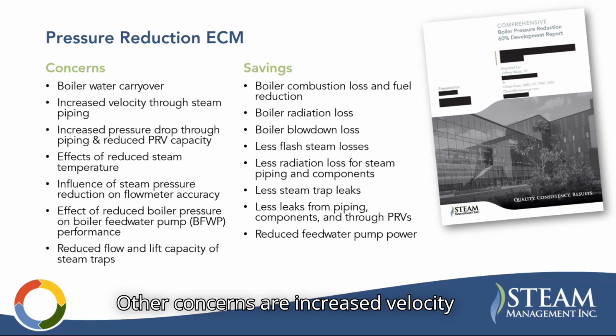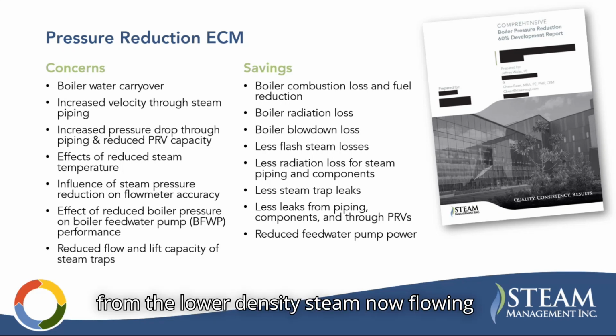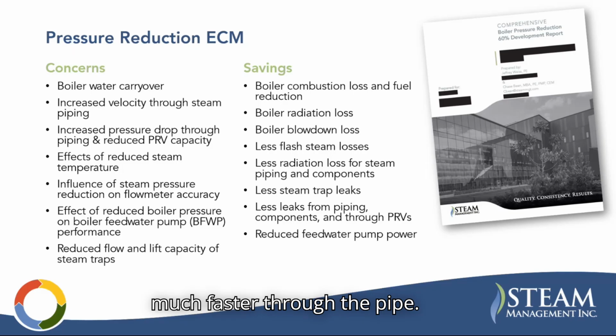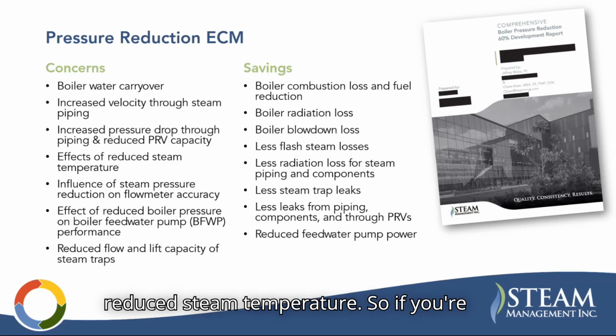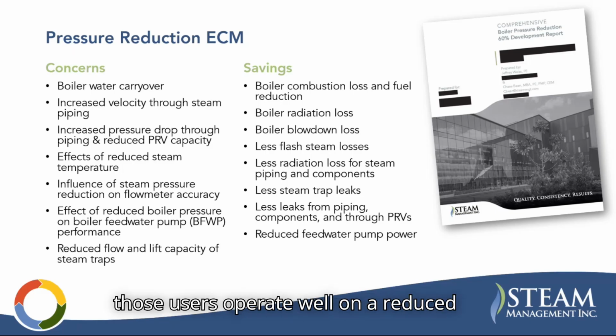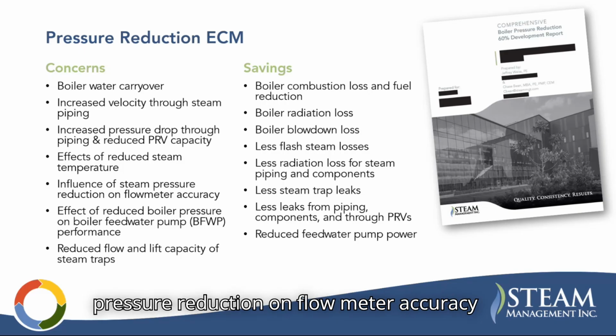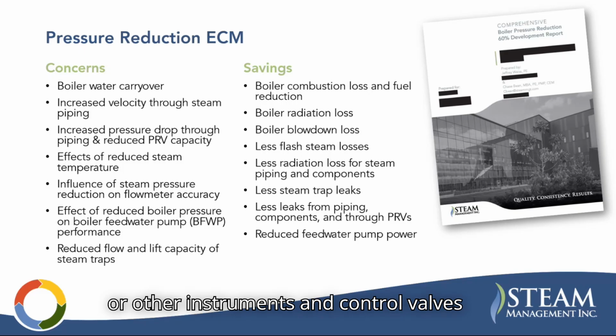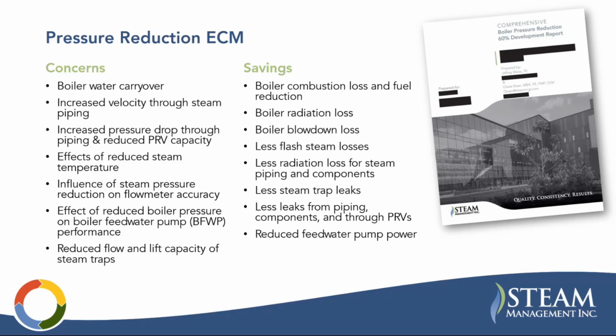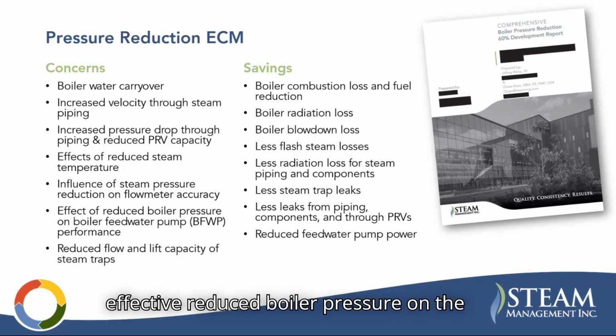Other concerns: increased velocity from the lower density steam now flowing much faster through the pipe. Increased pressure drop due to that increased velocity. Effects of reduced steam temperature. So if you're reducing the pressure that's actually supplied to your users, can those users operate well on a reduced temperature? The influence of steam pressure reduction on flow meter accuracy or other instruments and control valves. Effect of reduced boiler pressure on the boiler feed water pumps.